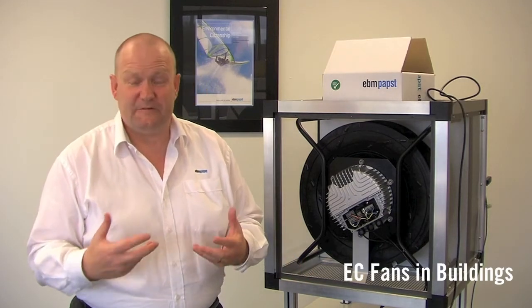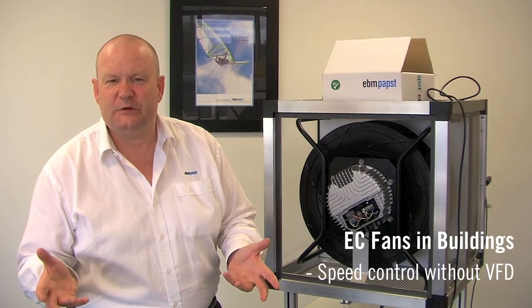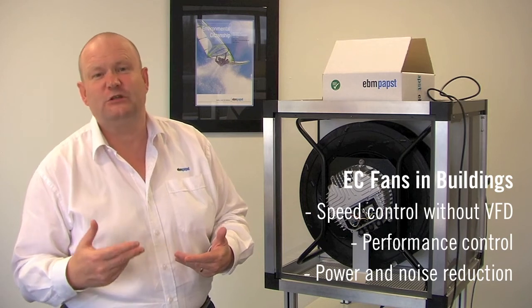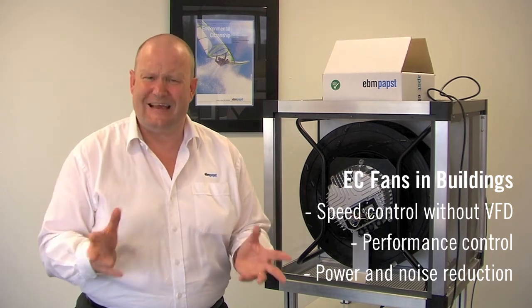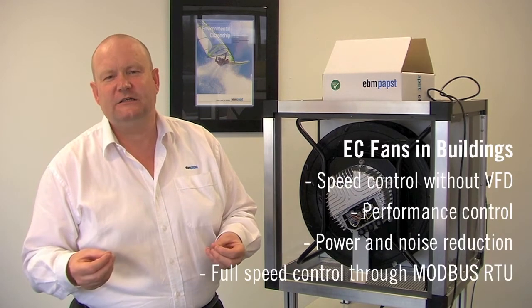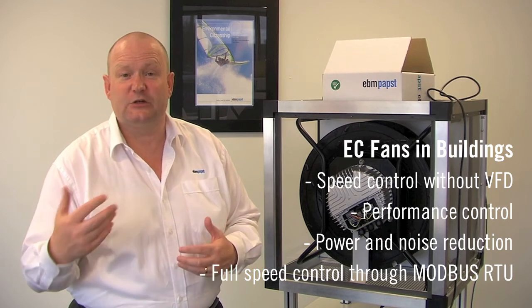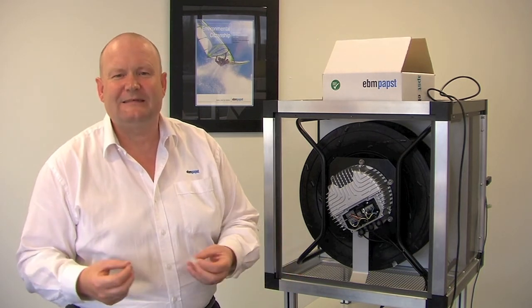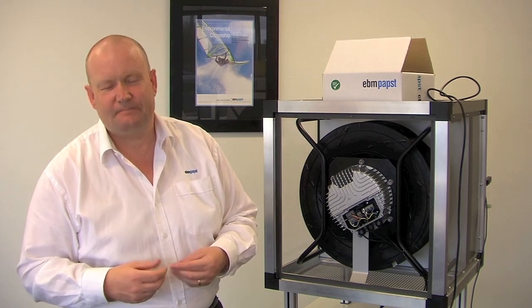To summarize: first, EBM Papst EC fans have speed control without the requirement for a variable frequency drive. Second, why do we want to speed control? We want to control the performance of the fan, reduce the power of the fan, and reduce the noise of the fan. Third, what's the best way of speed control? The best way is handshaking — using Modbus RTU control — which allows full communication between the controller and the fan. The controller asks the fan to do 50% and the fan tells the controller it's doing 50%. This is exactly the fine performance control needed in modern buildings. Thanks very much.